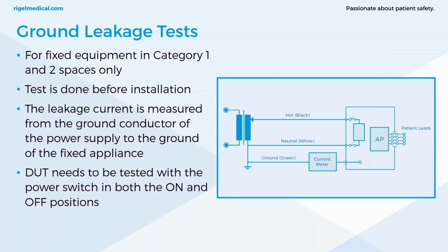So we've got ground leakage tests. These are not going to be performed as often as your other leakage tests. They're only specified for fixed equipment in category 1 and category 2 spaces only, and that's before you install the equipment. Now to ensure that all the leakage current flows to the measurement circuit of the safety analyzer, this test is done before any grounds are connected. So you're performing this before you actually install the device. You're just testing the ground leakage before you've installed it.